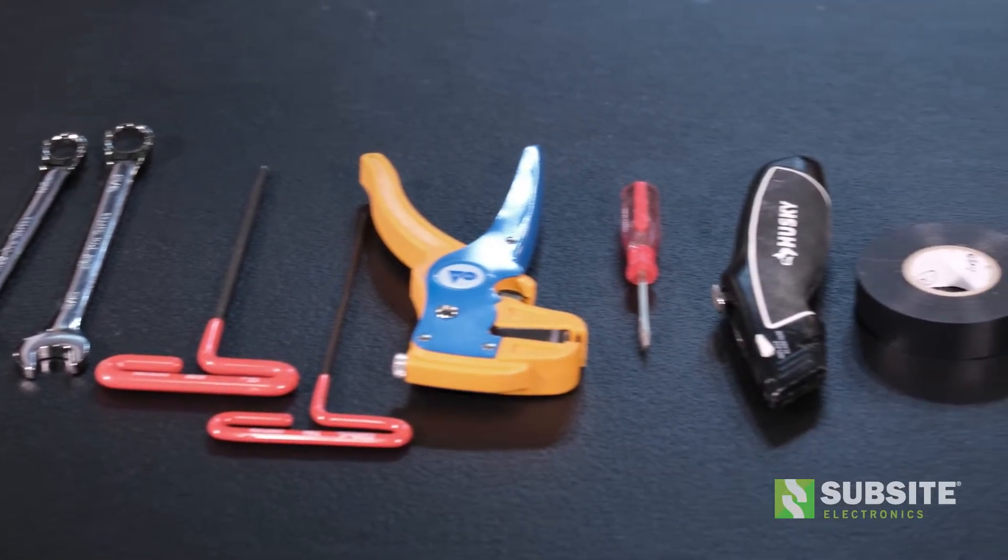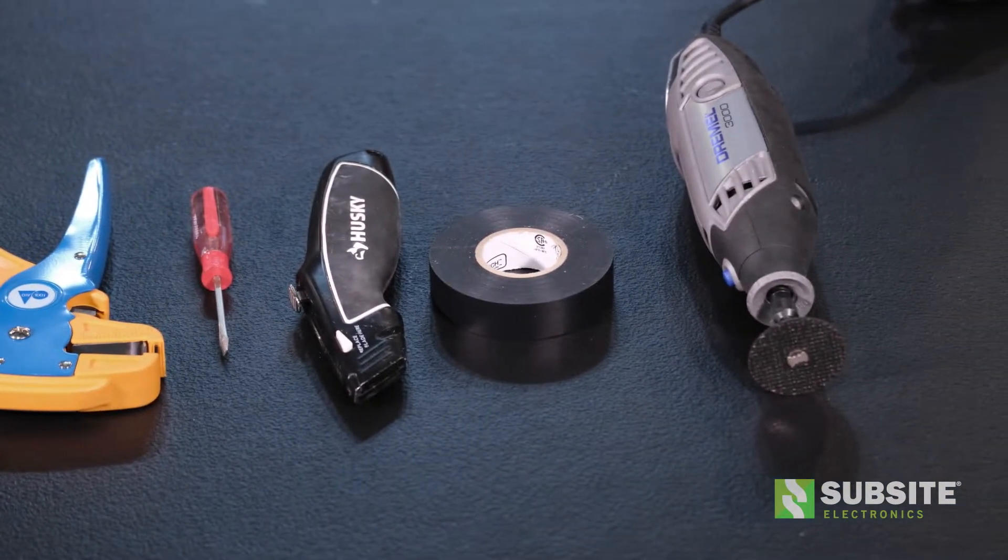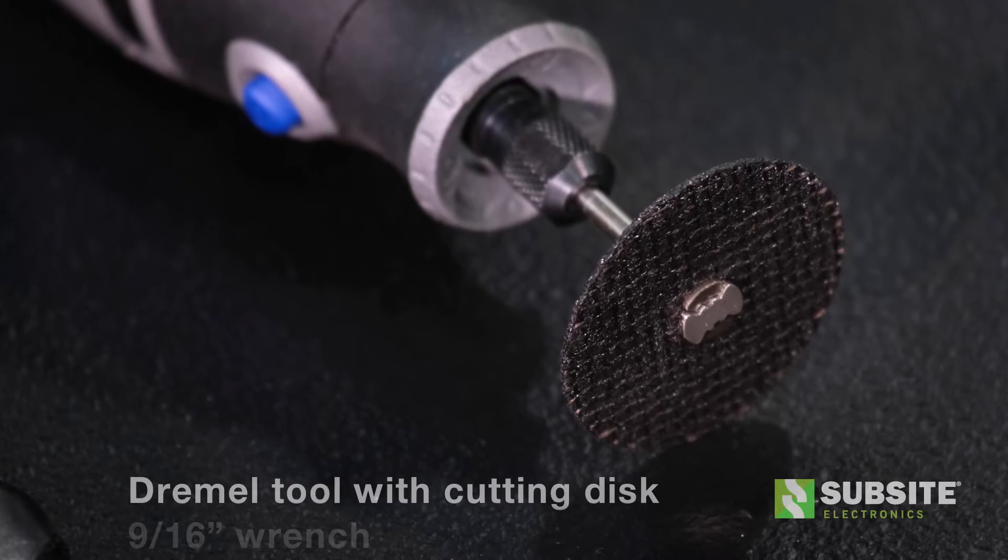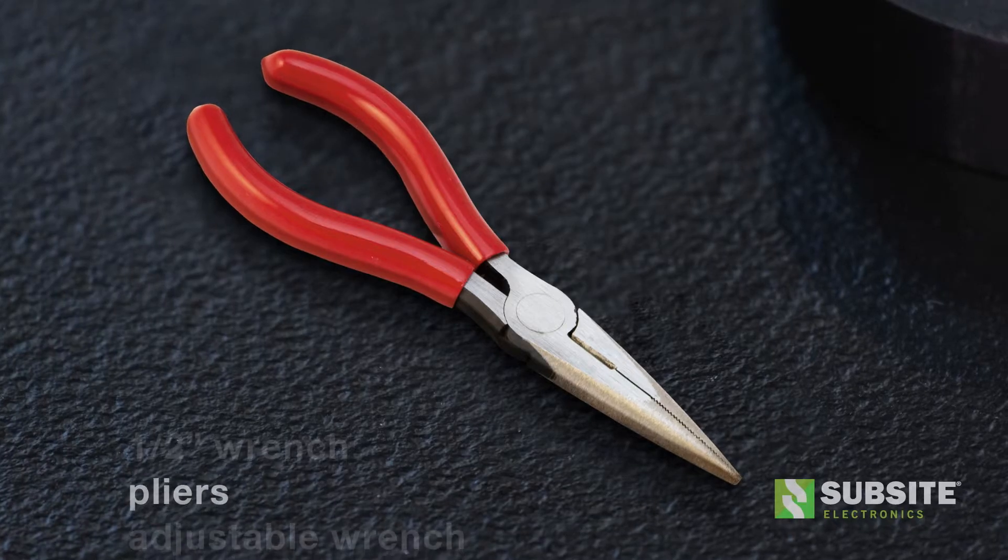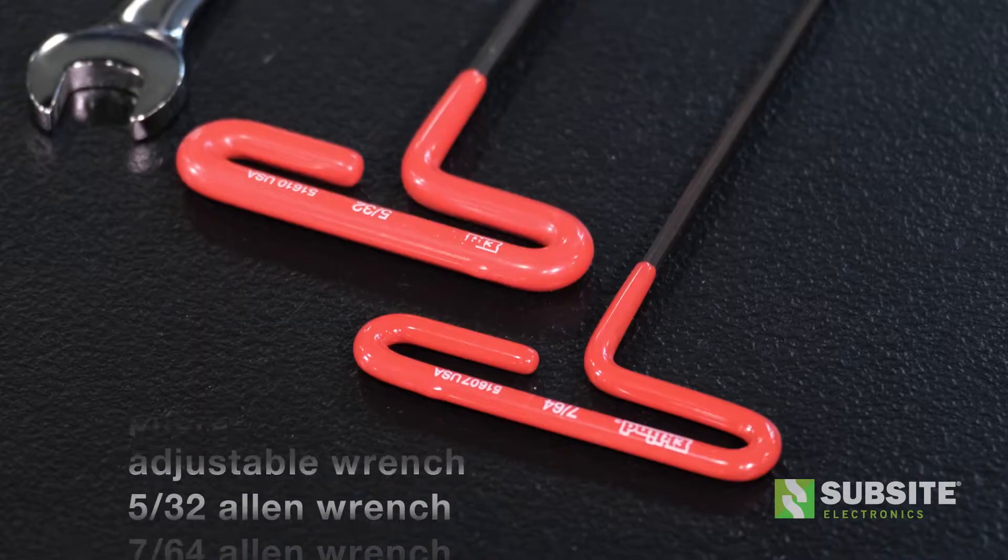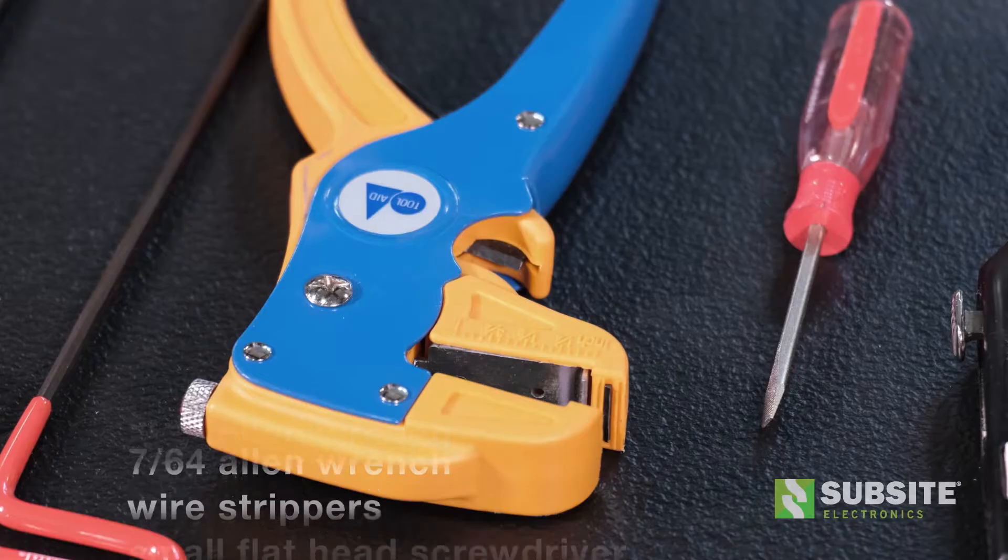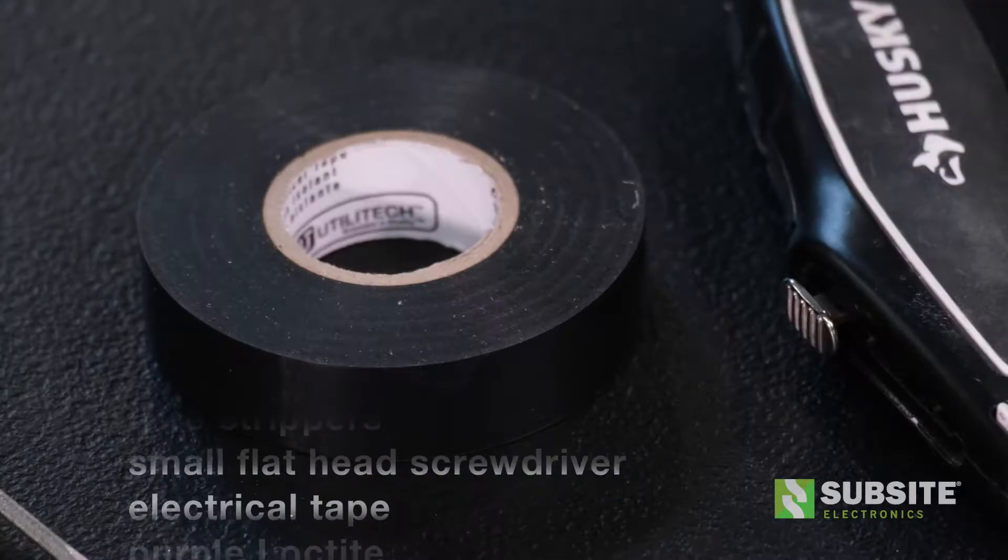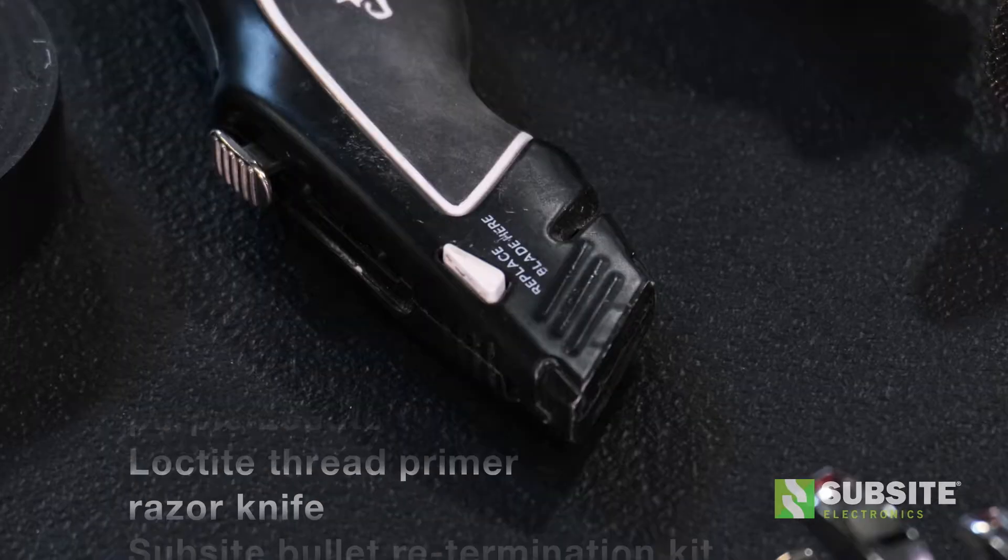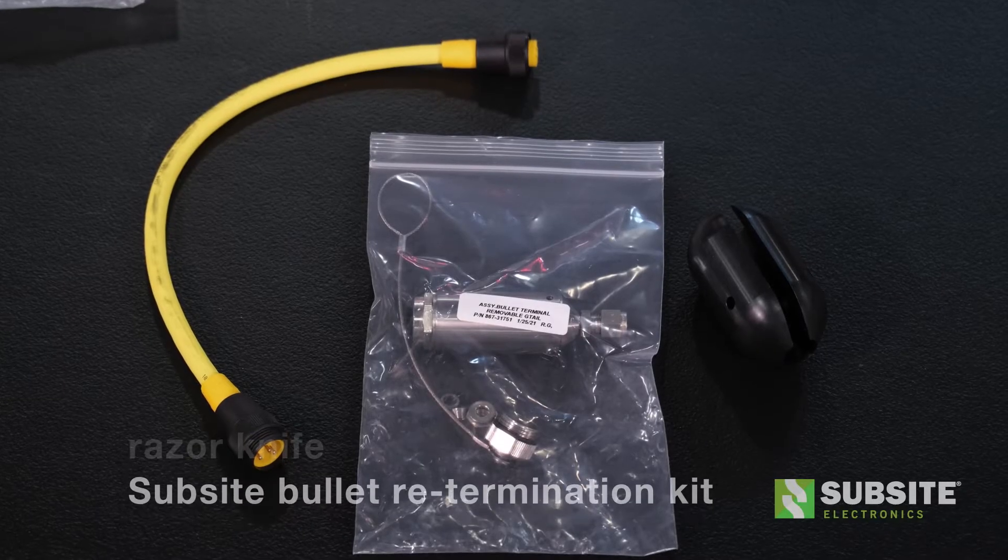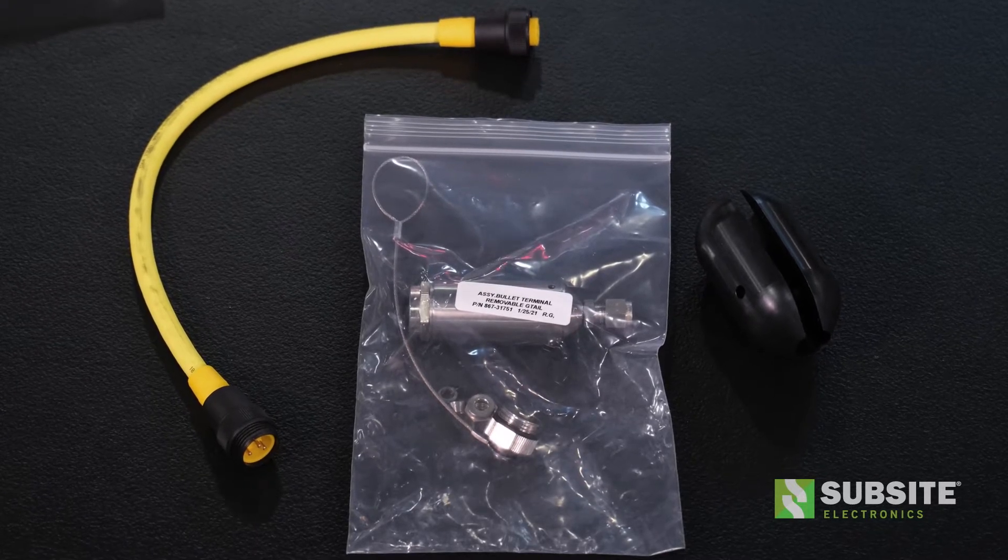Gather all the tools and accessories necessary to re-terminate the cable prior to beginning this process. These include a Dremel tool with cutting disc, 9/16 inch wrench, half inch wrench, pliers, adjustable wrench, 5/32nds Allen wrench, 7/64ths Allen wrench, wire strippers, a small flathead screwdriver, electrical tape, purple Loctite, Loctite thread primer, razor knife, and a Subsite bullet re-termination kit. Refer to your Subsite parts catalog for the part number.